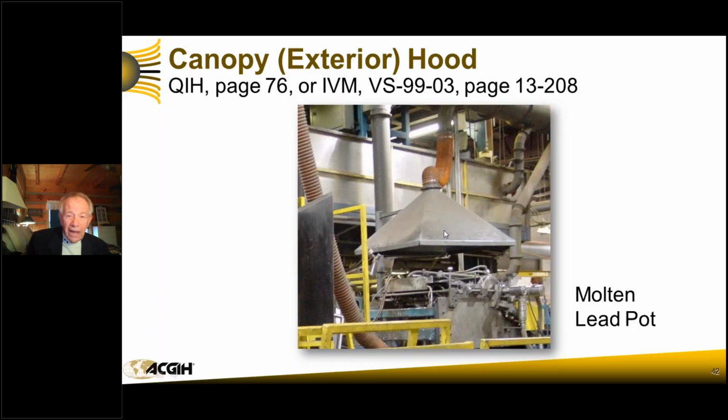This is actually one that I did back in my lead days. Notice how this should have been a very short piece of flex hose, which Greg is going to talk about later, about the losses that are significantly more, not to mention the extra elbow here and the extra elbow there.